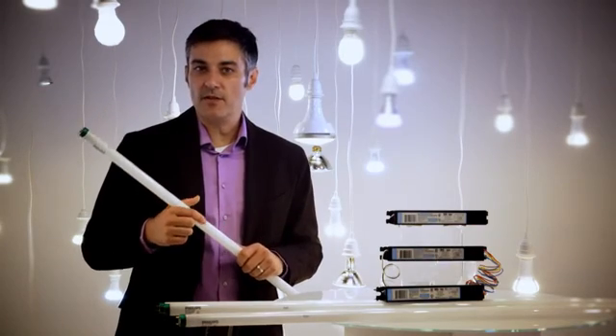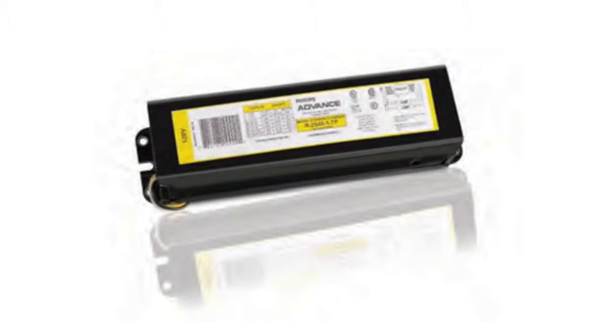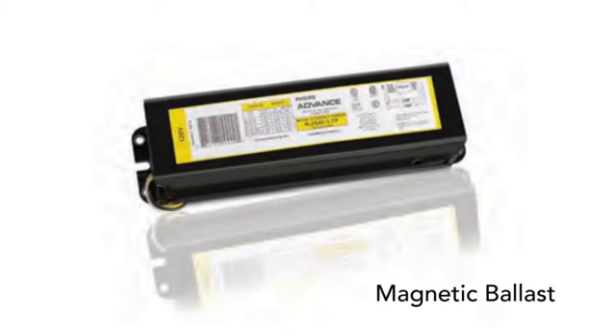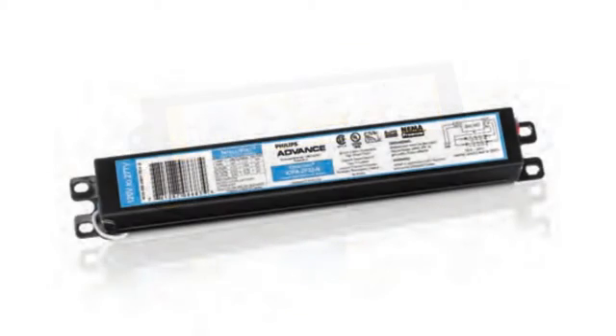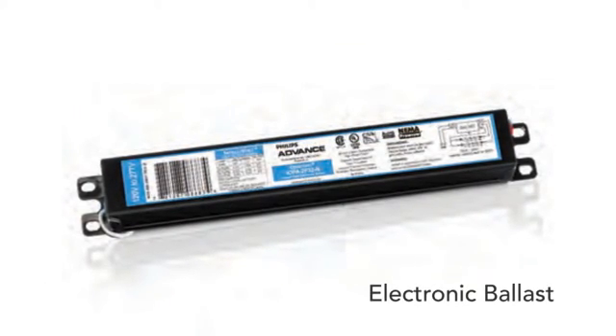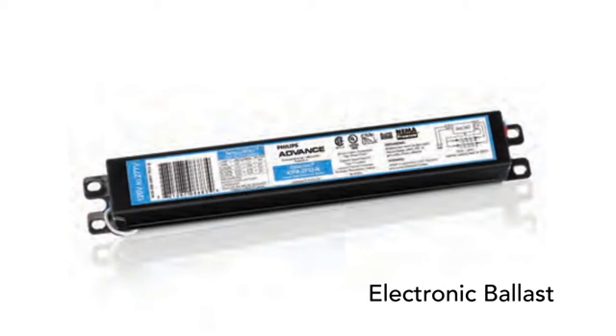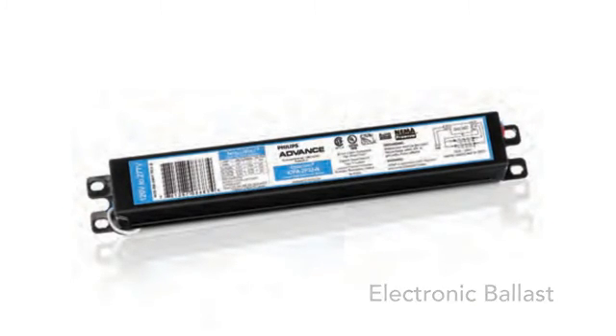There are two types of ballasts for residential fluorescent bulbs. The oldest in use is the magnetic ballast, almost all of which were phased out by Department of Energy legislation in 2010. The lighter, quieter, and more energy-efficient electronic ballasts are the smart replacement for magnetic ballasts.